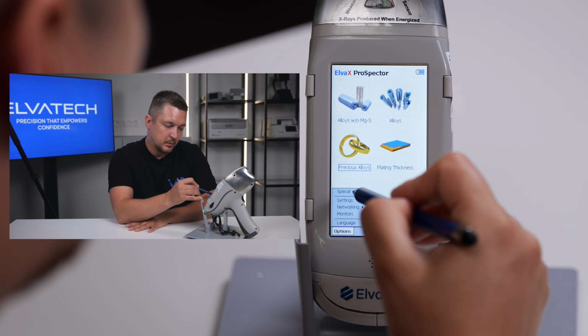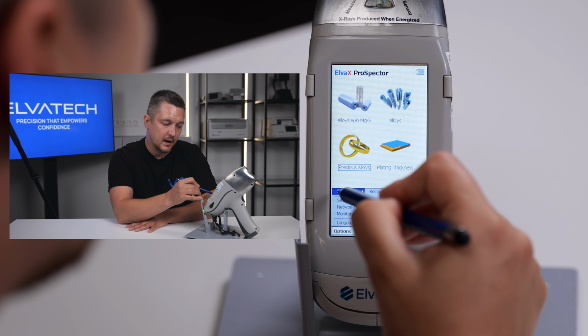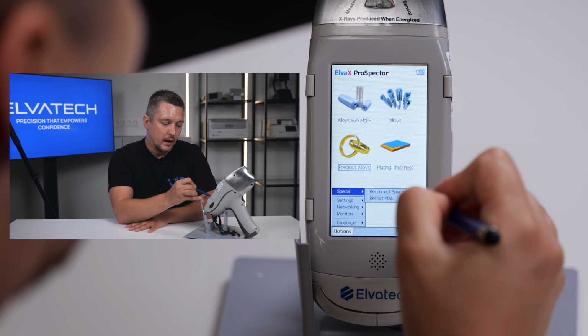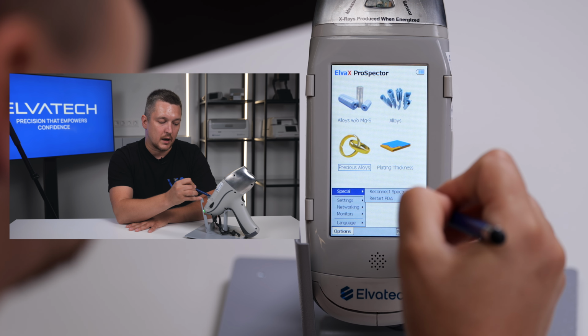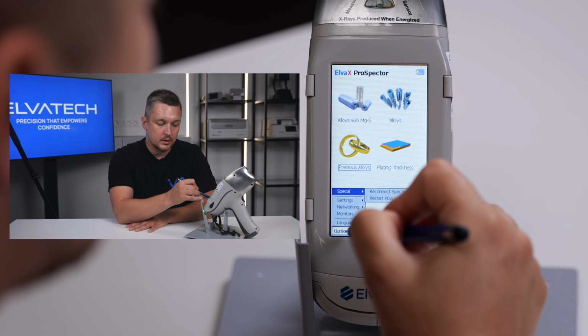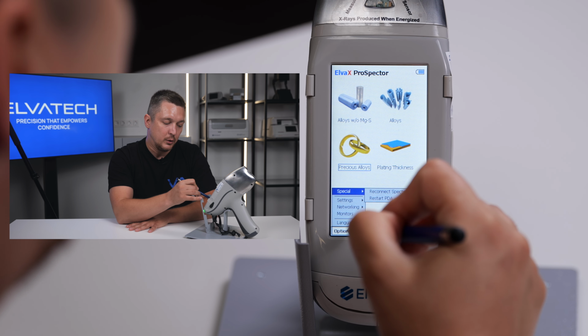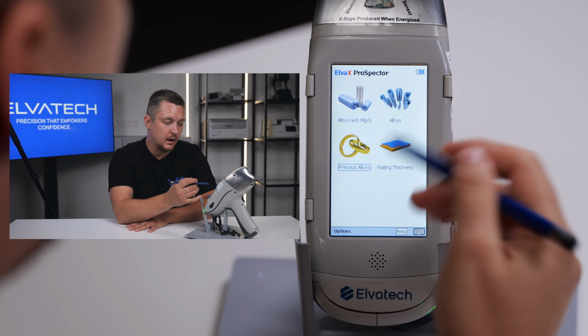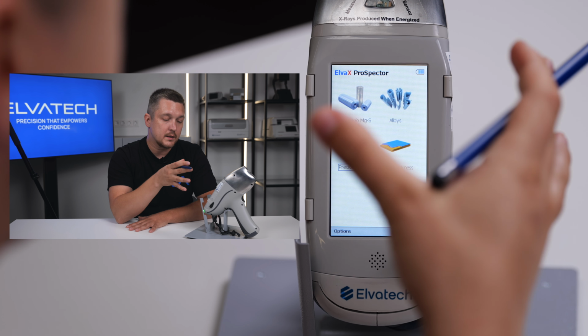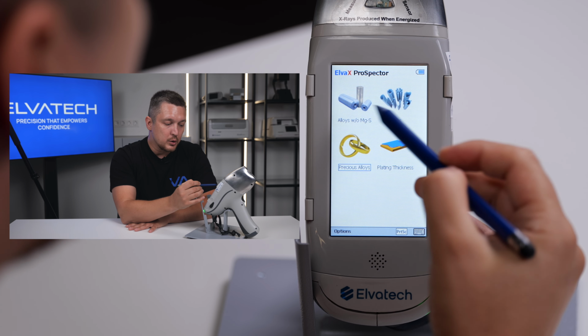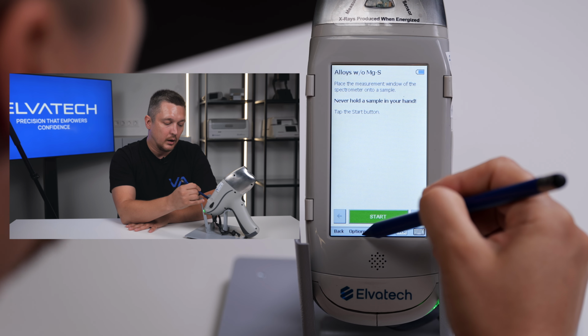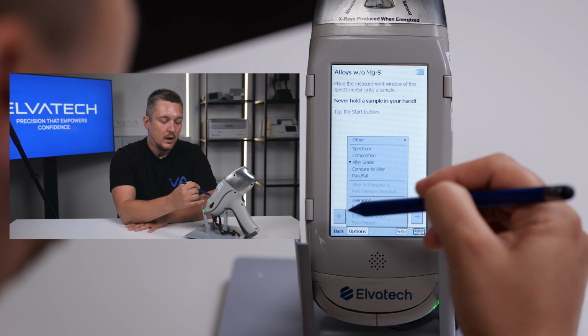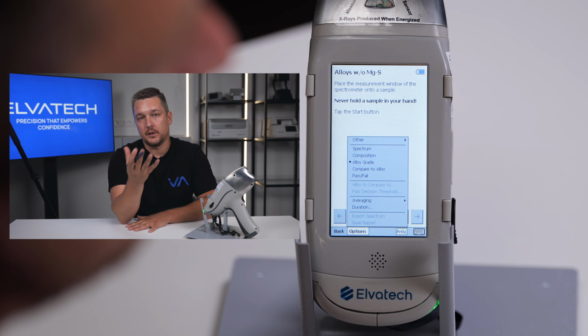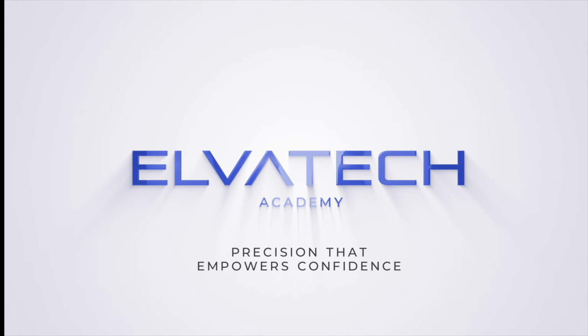And the last submenu, we have the special. Here you see the Reconnect spectrometer and Restart PDA options that our service department uses, and you don't need them. So it was the main menu of the analyzer, but also we have additional menus in every calibration that we will cover in our next videos.